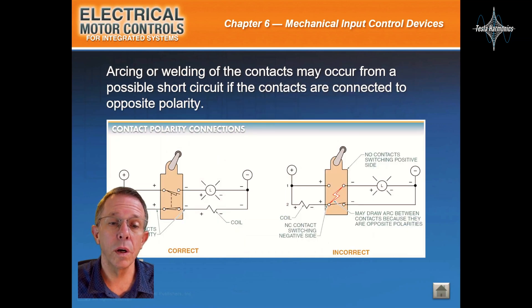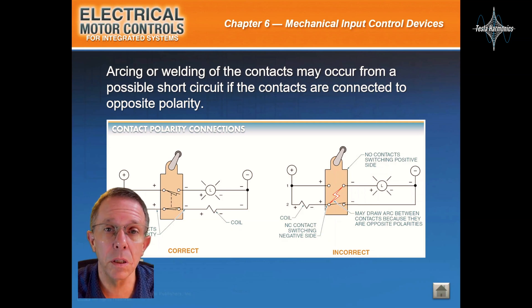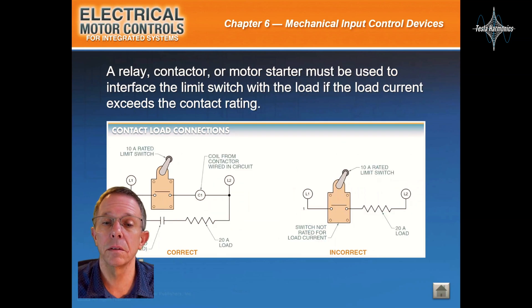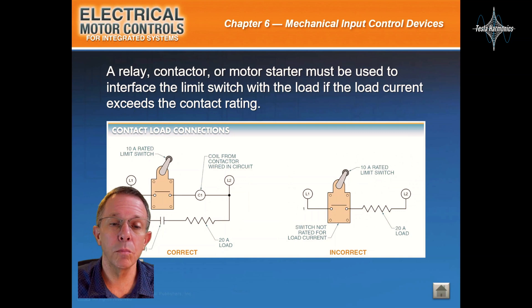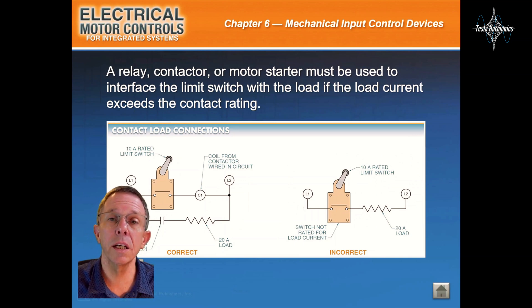Arcing or welding of the contacts may occur from a possible short circuit if the contacts are connected to the opposite polarity. A relay, contactor, or a motor starter must be used to interface the limit switch with the load if its load current exceeds the contact rating.